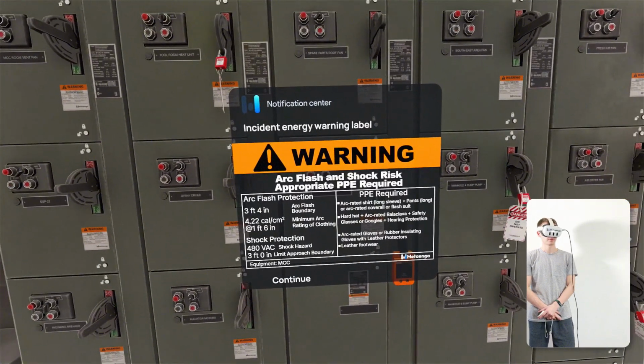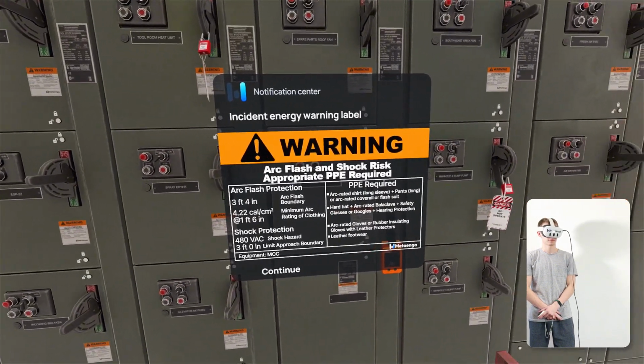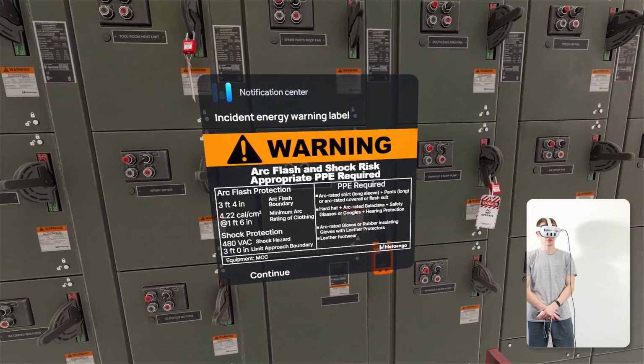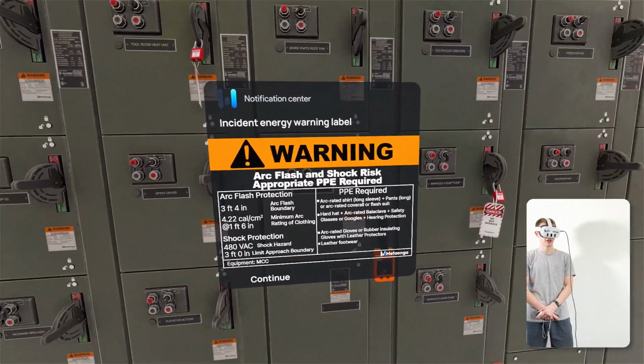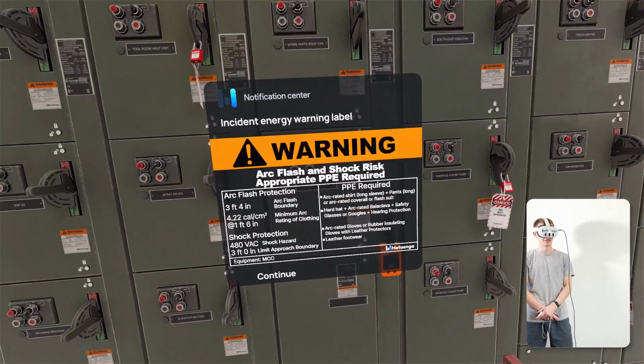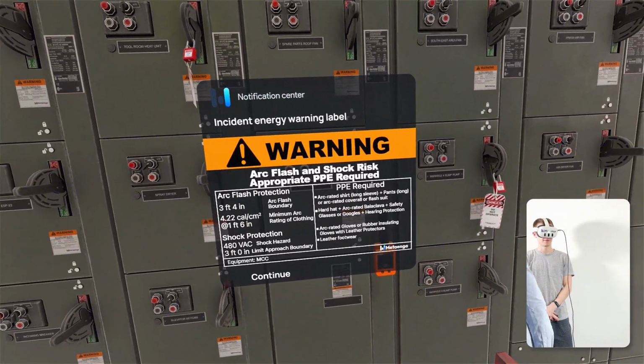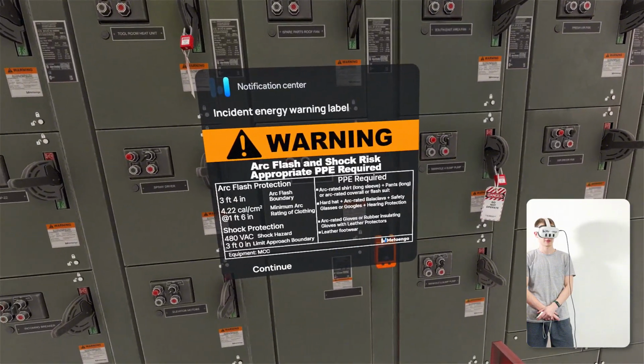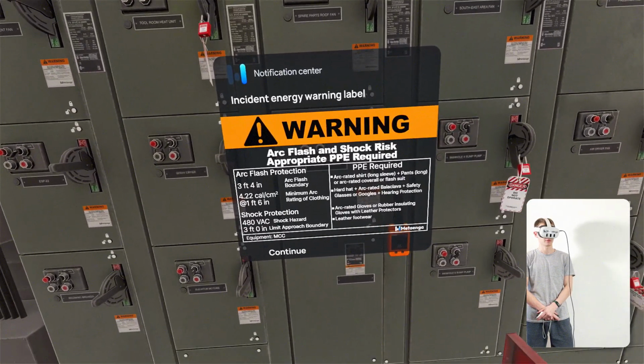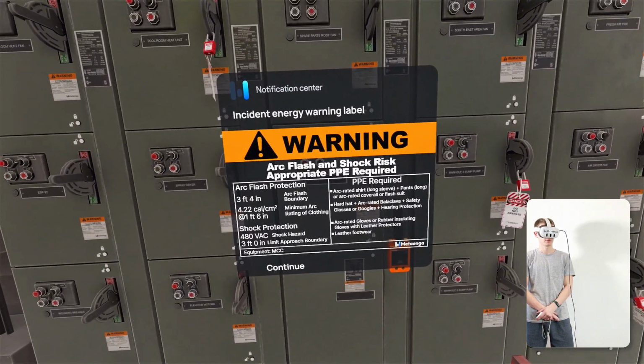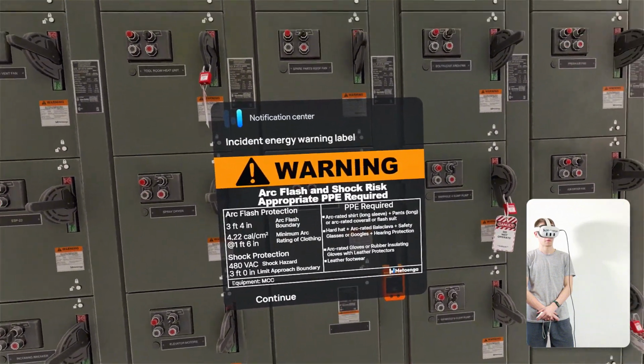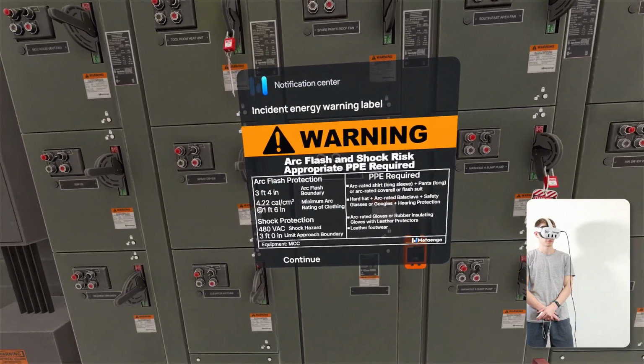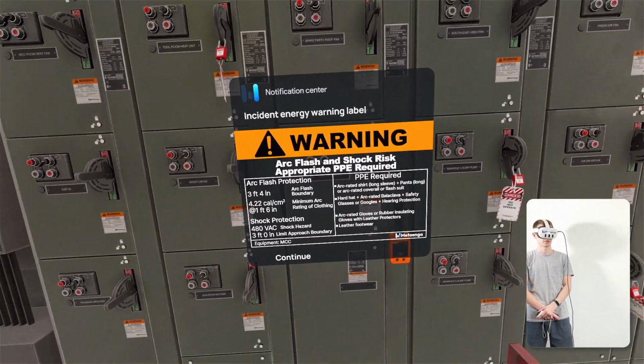Let's focus on the left side of the label. You'll see it states an arc flash boundary of 3 feet 4 inches. This marks the safe working distance to prevent serious burns in case of an arc flash. The label also specifies 4.22 calories per square centimeter at 1 foot 6 inches, indicating the amount of incident energy you could be exposed to at that distance and the required arc rating for your protective clothing.